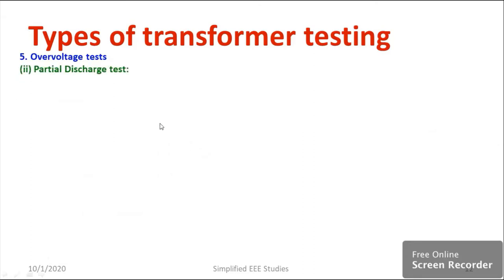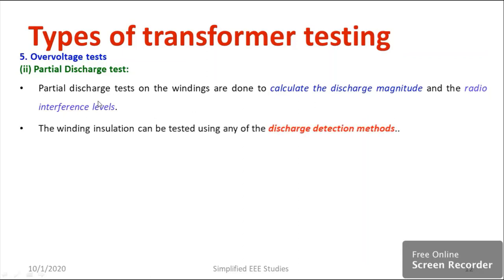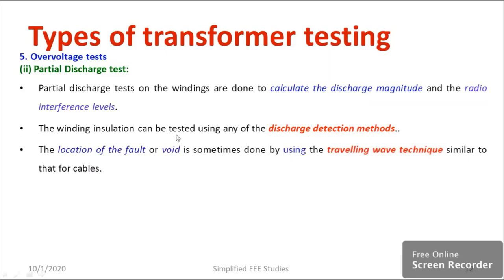I would like to discuss the partial discharge test. The purpose is to calculate the discharge magnitude and the radio interference level. The winding insulation can be tested using any discharge detection method — there is no standard rule. You can go for the straight detector method, balanced detector method, or narrow and wide band frequency method. Location of fault or void is sometimes done using traveling wave methods.